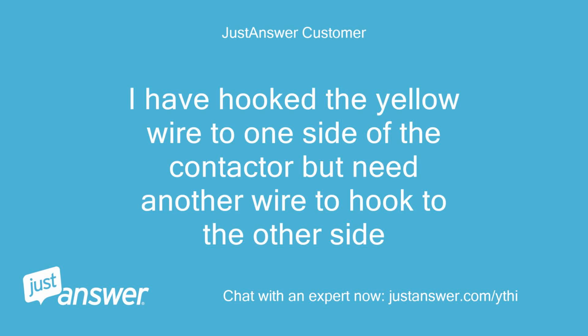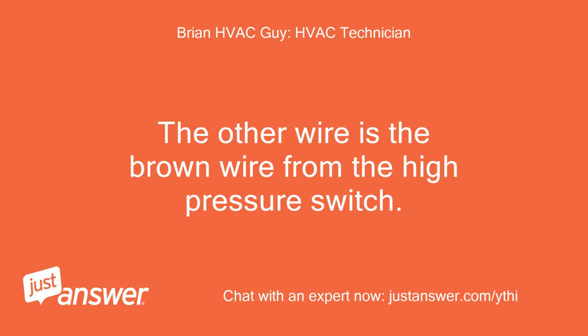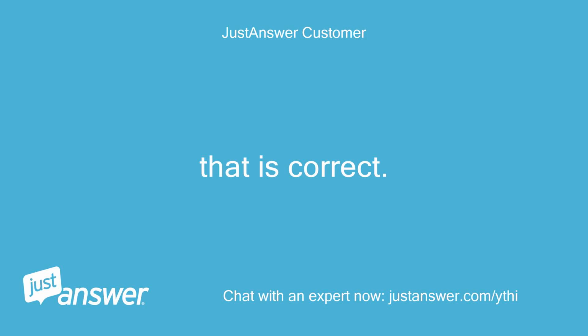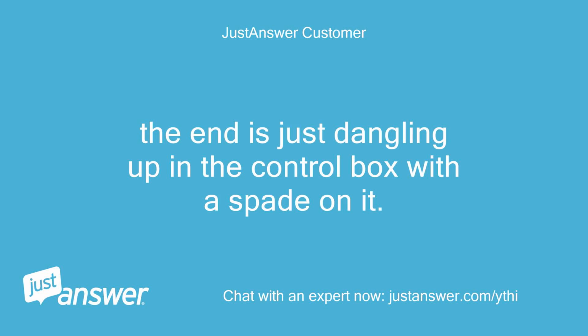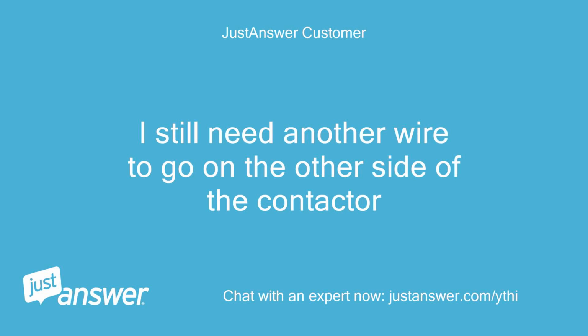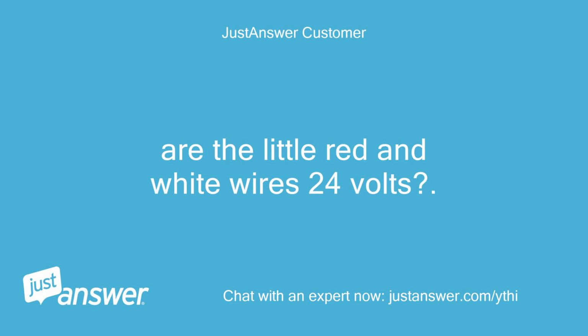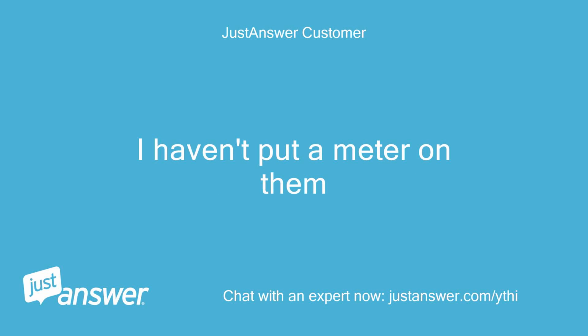I have hooked the yellow wire to one side of the contactor but need another wire to hook to the other side. The other wire is the brown wire from the high pressure switch. That is correct. The end is just dangling up in the control box with a spade on it. I still need another wire to go on the other side of the contactor. Are the little red and white wires 24 volts? I haven't put a meter on them.